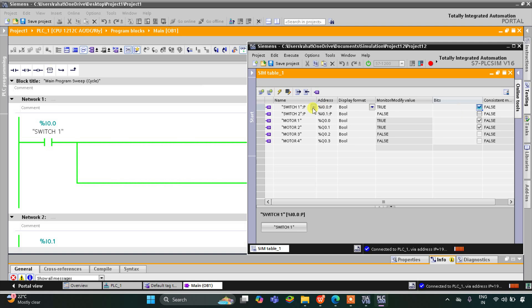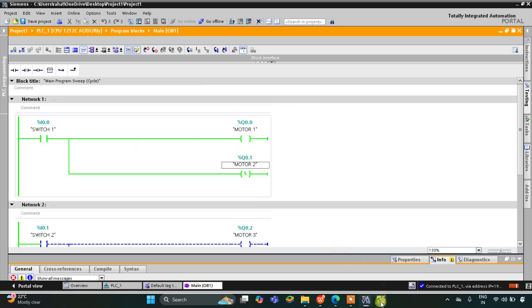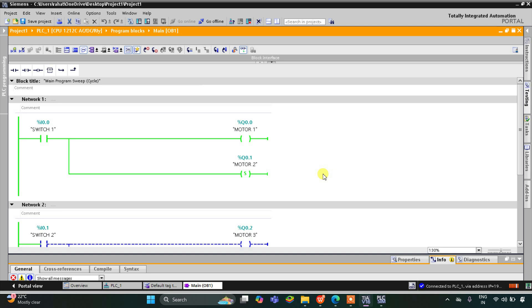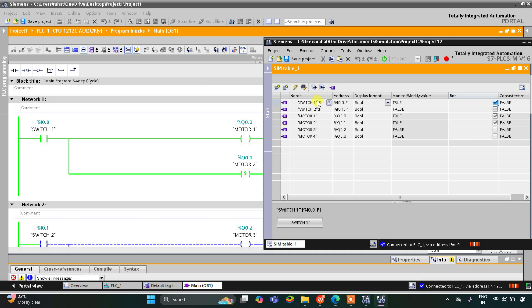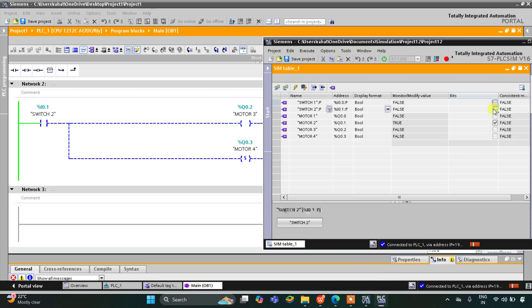When I turn on Switch 1, Motor 1 and Motor 2 get on. As you can see, Switch 1 is on, Motor 1 and Motor 2 are on. You can also see in the ladder that when Switch 1 is true, Motor 1 and Motor 2 are both on. When I turn it off, Motor 1 is off but Motor 2 still remains on — you can see the green color — due to this set coil, Motor 2 still remains on.